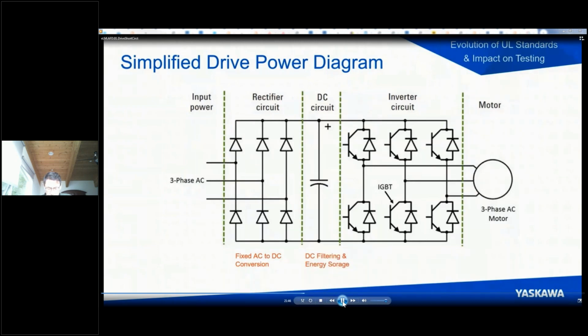And the next section is the DC bus, and generally consists of a bunch of bus capacitors to store and filter the energy. And then the last section is chopping up the DC bus back into variable AC to control the motor. And we're going to focus our discussion for the moment just on that center section, the DC bus section. I'm showing a single capacitor there, but often there's multiple capacitors in series and parallel combinations.